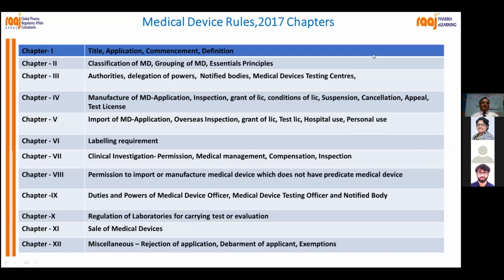Chapter 4 is manufacture of medical devices: application, inspection, grant of license, conditions of license, suspension, cancellation, appeal, and the investigational device test license. Chapter 5 relates to import of medical devices. If it is coming from some other country, then if required, that organization or manufacturing facility in that country will be inspected by DCGI. Grant of license, test license, and if it is for hospital use or personal use, how it can be imported. Chapter 6 is labeling requirements. Chapter 7 deals with clinical investigation, permissions, medical management, compensation in case of adverse events, and inspection of the site. Chapter 8 is permission to import or manufacture medical devices which do not have a predicate medical device. So if you are importing or manufacturing a device for the first time which does not exist or does not have a predicate device, what rules will be applicable?